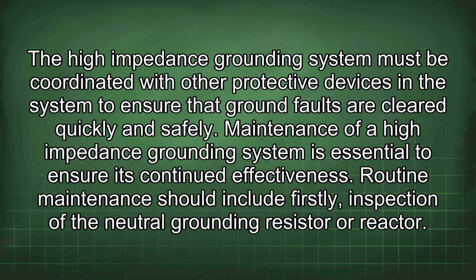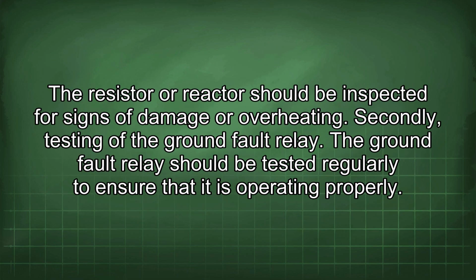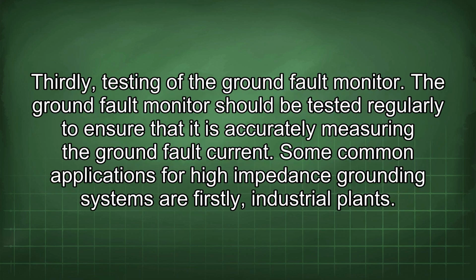Routine maintenance should include, firstly, inspection of the neutral grounding resistor or reactor. The resistor or reactor should be inspected for signs of damage or overheating. Secondly, testing of the ground fault relay. The ground fault relay should be tested regularly to ensure that it is operating properly. Thirdly, testing of the ground fault monitor. The ground fault monitor should be tested regularly to ensure that it is accurately measuring the ground fault current.